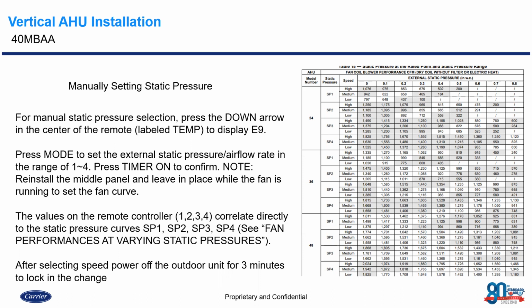And if you haven't been setting that up, then chances are that's probably why you got some return calls on why the unit's not delivering the correct amount of airflow. And typically, you probably would have talked to me and then found that you actually have to set that up. So it's always important to reference the static pressure and CFM charts depending on what program you want to run that at, depending on what CFM the space needs. Okay, so 2 options on there.